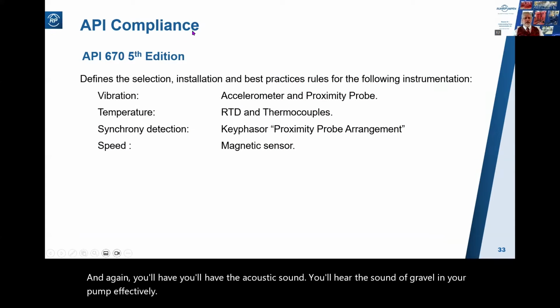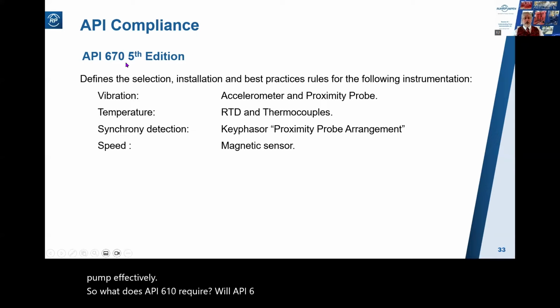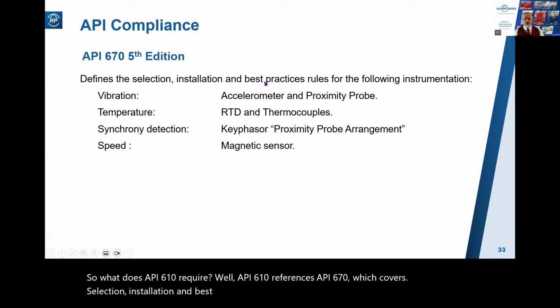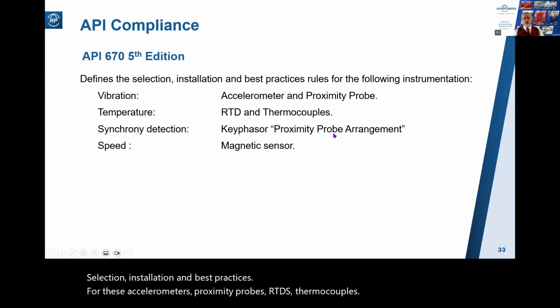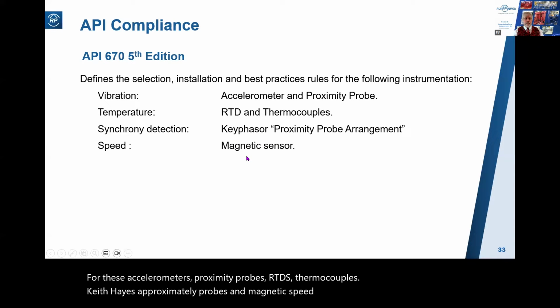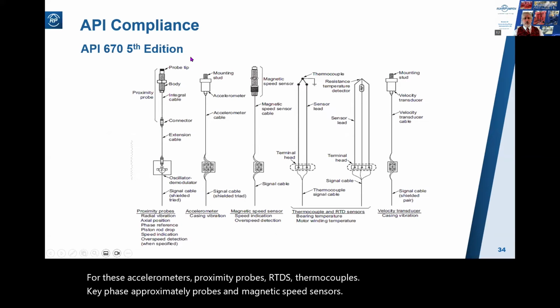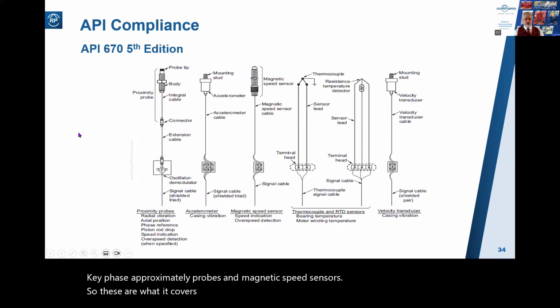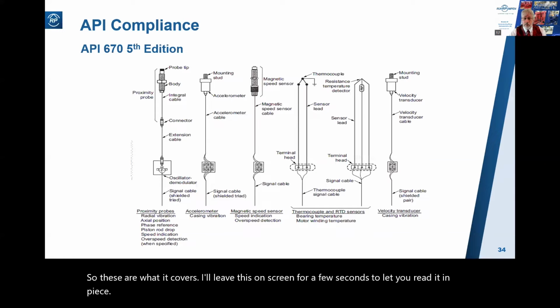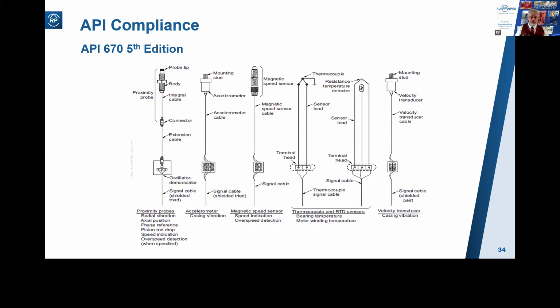So what does API 610 require? Well, API 610 references API 670, which covers selection, installation, and best practices for these: accelerometers, proximity probes, RTDs, thermocouples, Keyphasor proximity probes, and magnetic speed sensors. So these are what it covers. I'll leave this on screen for a few seconds to let you read it in peace. So API pump suppliers will be complying with API 670 for these items.